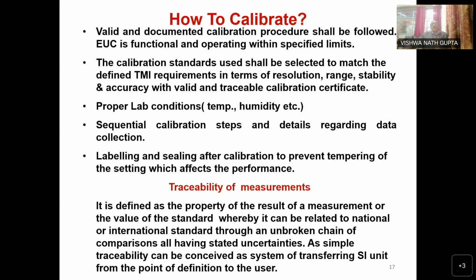See, generally we write in the calibration certificate that the certificate is valid for the instrument with the serial number, and that it has been calibrated in laboratory conditions. That's why the sealing is required, so that if any tampering happens, your calibration certificate is not valid anymore. Now, here, traceability of measurements.